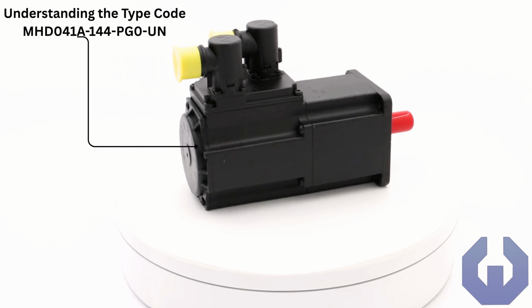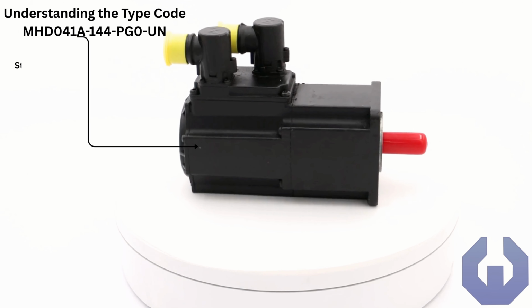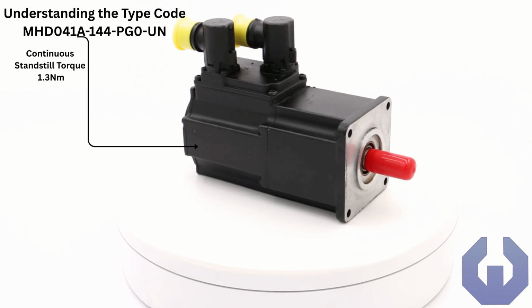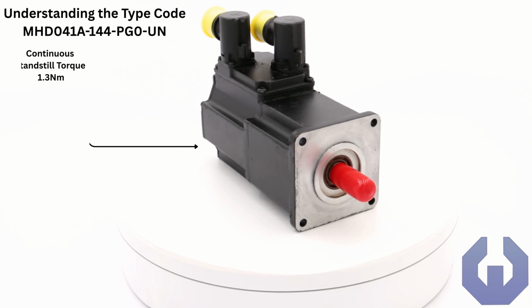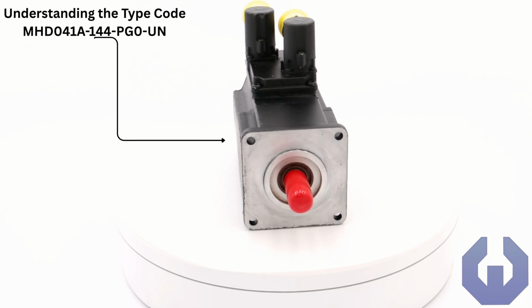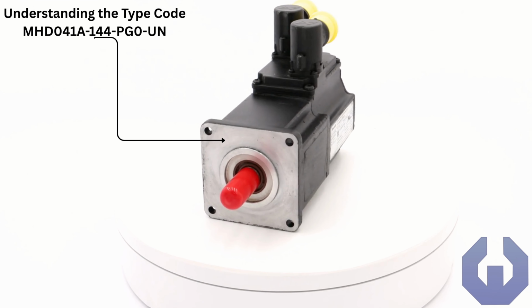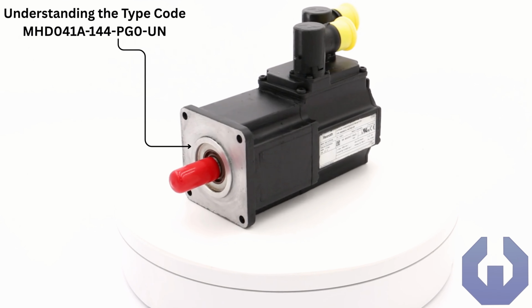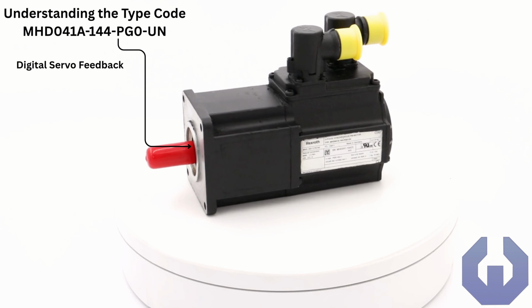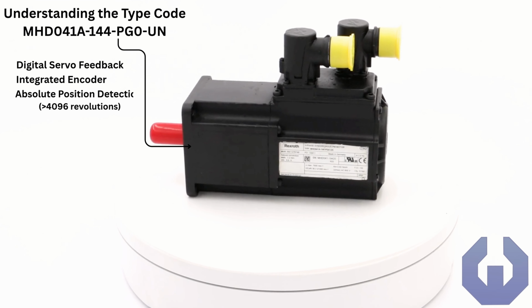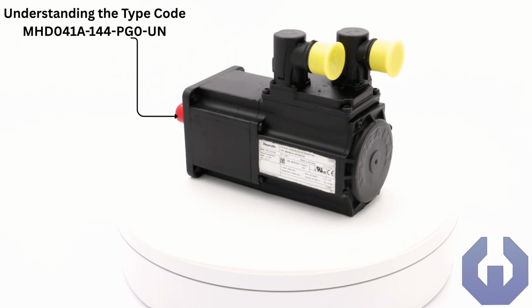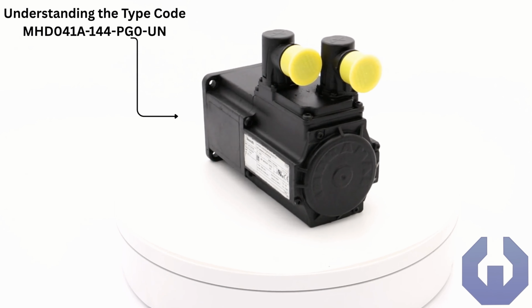A denotes a motor length of A. It has a continuous standstill torque of 1.3 Nm. 144 means the winding code for the motor is 144. P denotes the motor has digital servo feedback with an integrated encoder and absolute position detection. G denotes the shaft is plain and with a shaft seal present.